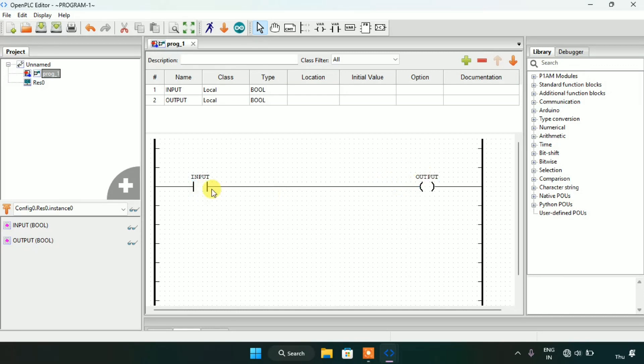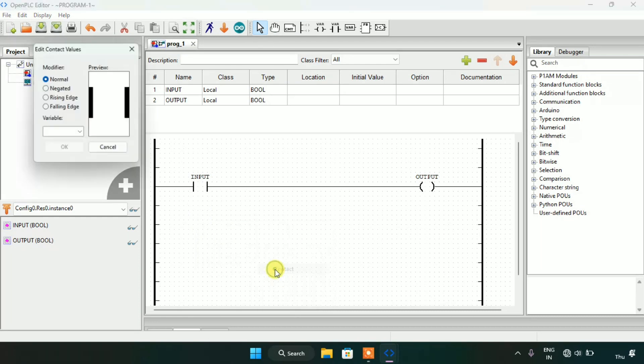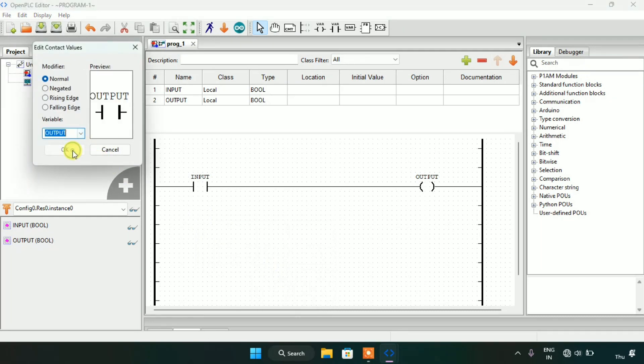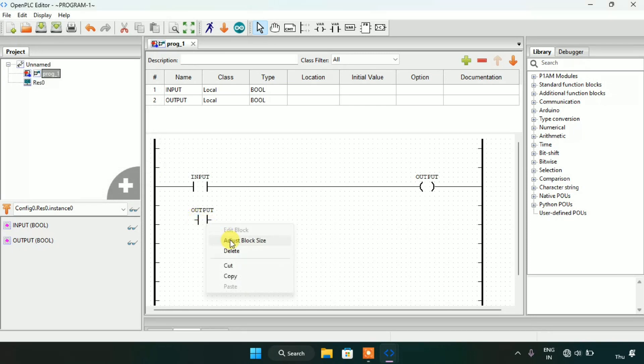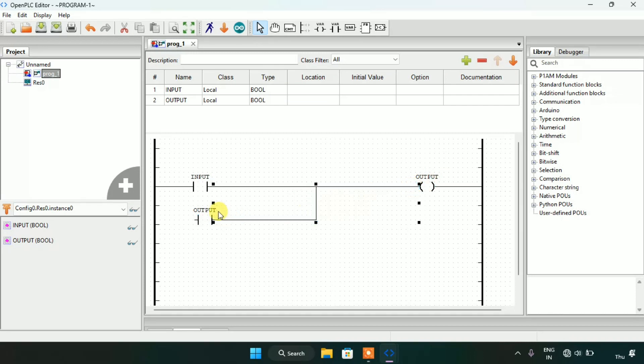And when I modify the input as false the output will go false. Now, how to make a push button — I only need to add a contact and address the contact with the same address as the coil. What you see here is a concept known as latching, which means if I address the input the same as the output and use the output as an input, this is known as latching.